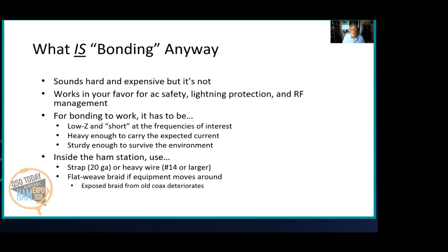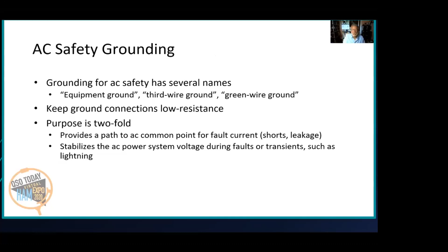It basically has several names: equipment ground, third wire ground, green wire ground. It needs to be a low resistance connection, because it only has two purposes. It provides a path back to the AC common point for fault currents like short circuits or leakage from compromised insulation or excess capacitance. The other thing it does is it helps stabilize the power system voltage during faults or transients, such as a lightning strike on the power system, which happens all the time. But only those two things, that's all it's there for.